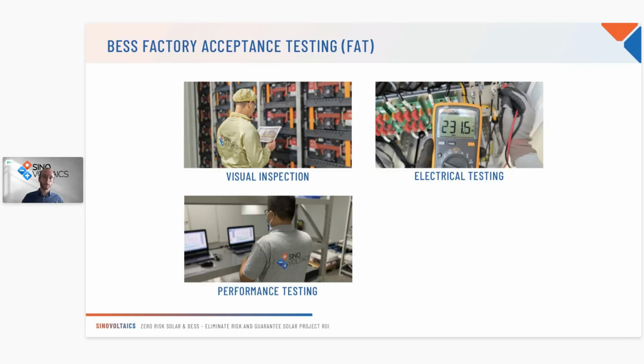After that, we'll have a full performance testing, making sure the entire system is working correctly at full charge or full discharge, for a full cycle, both charging and discharging. You want to make sure everything is working correctly here, because it's kind of the first time the energy storage system is working together.